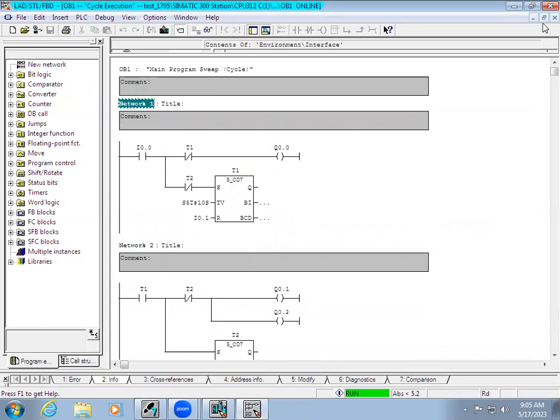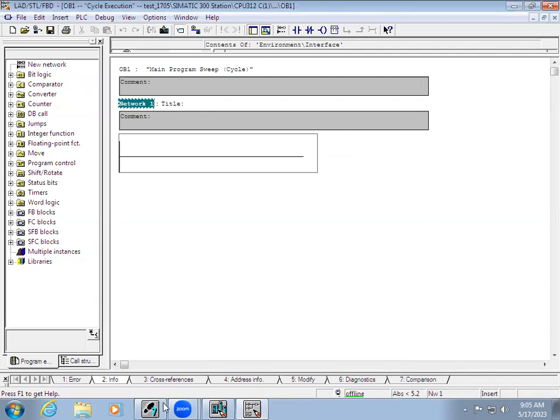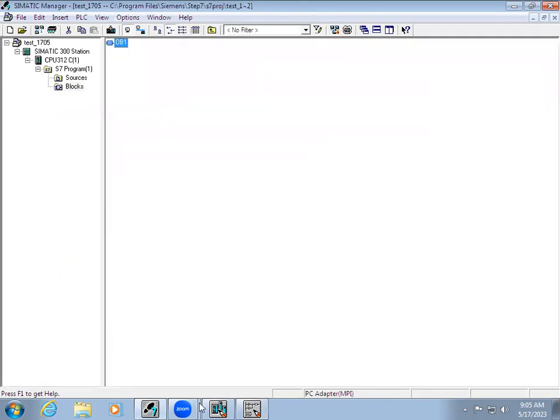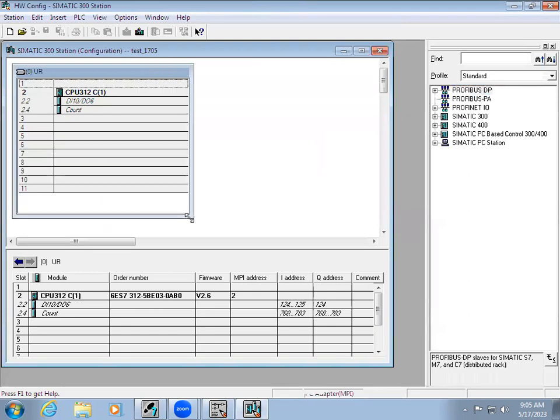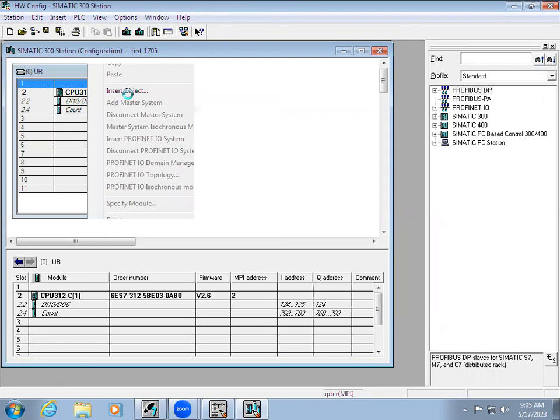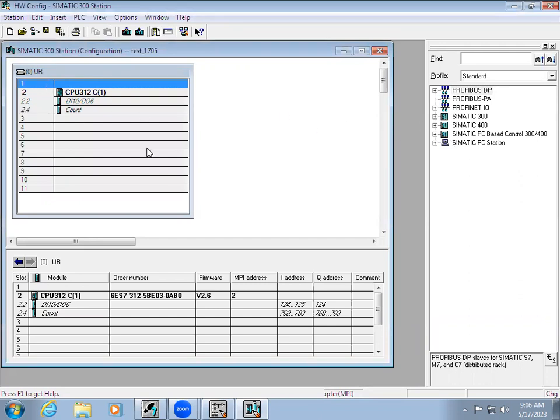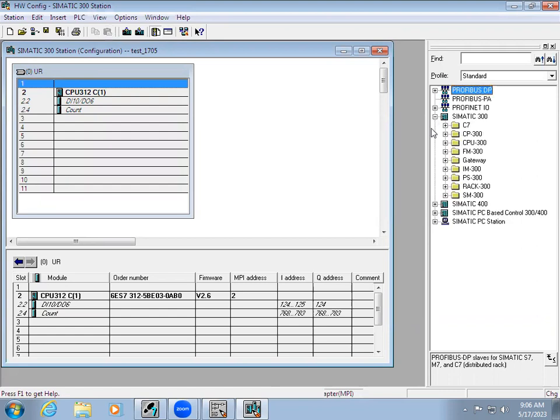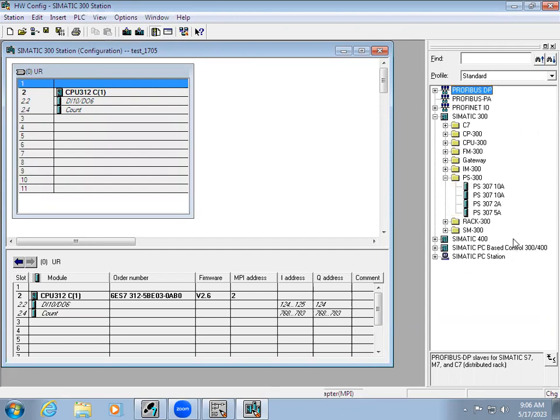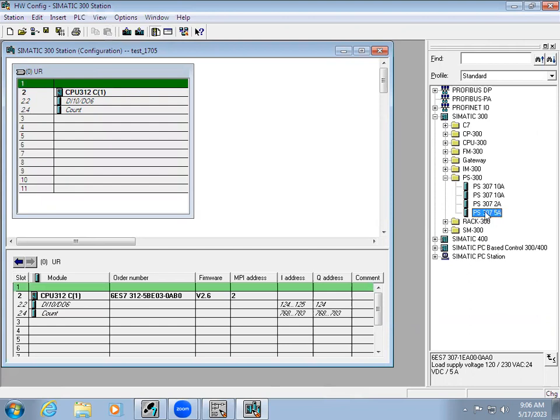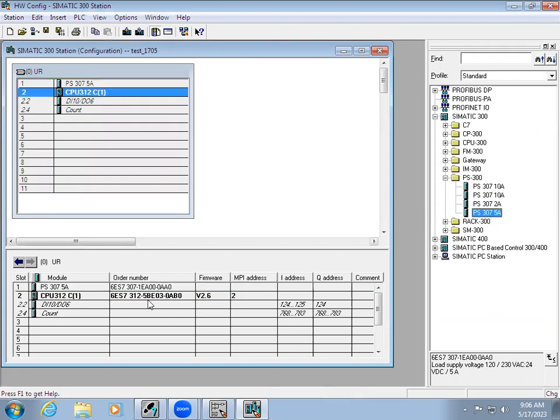If you are doing a new project, we have to do the hardware configuration. In Simatic Manager go to Hardware. Since when creating the project we selected the CPU number it will show it. Right-click Insert Object and it will show you the power supply module. You can see the order number when you hover the cursor over it. Another option is, since we are using a Simatic 300 station, on the right-hand side we have the Catalog — expand PS 300 which is the power supply module — and from there you can select it by double-clicking.